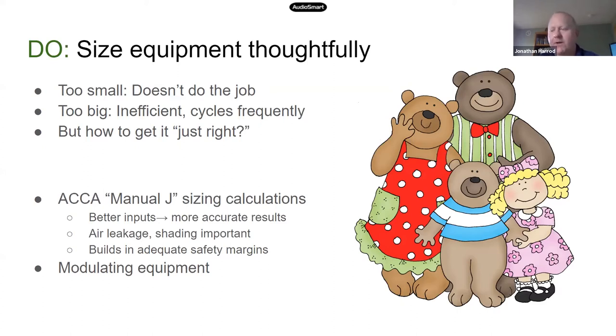To do that, we follow an industry standard procedure. The Air Conditioning Contractors of America created a series of manuals, and the one that we use to determine how much heating or cooling a house needs is their Manual J. It's essentially a spreadsheet where you put in all the characteristics of the house, the window areas, the window types, wall insulation levels, and so forth. And it will tell you, okay, this house needs so many BTUs to keep it warm on the coldest day that you're likely to experience. The better the information that you put into this calculation, the better results you'll get out of it.